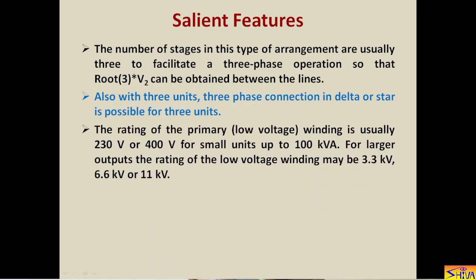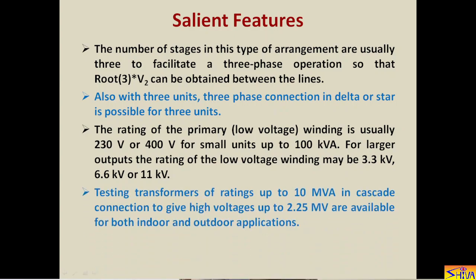The rating of the primary or low voltage winding is usually 230 V or 400 V for small units up to 100 kVA. For larger outputs the rating may be 3.3 kV, 6.6 kV, or 11 kV. Testing transformers of rating up to 10 MVA in cascaded connection can give high voltages up to 2.25 MV (i.e., 2250 kV) and are available for both indoor and outdoor applications.